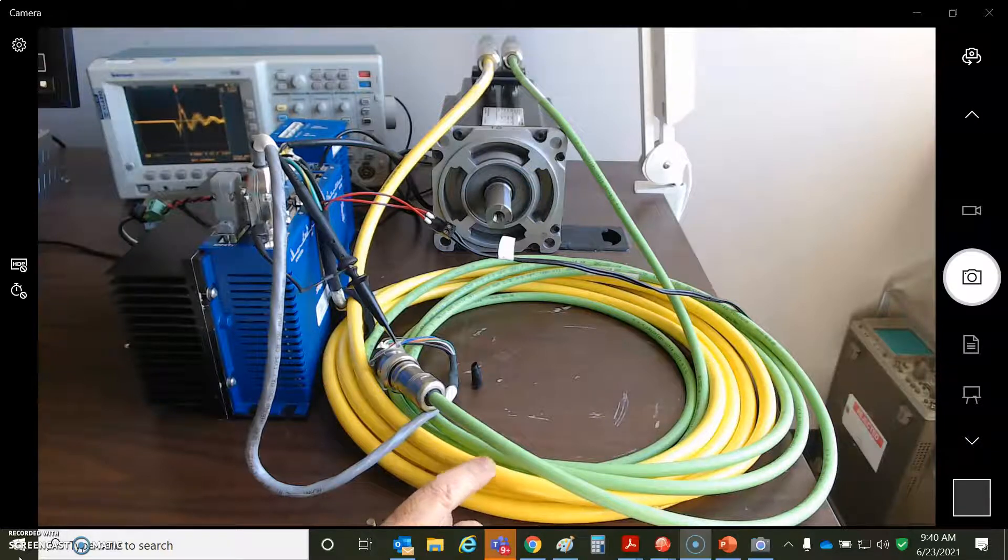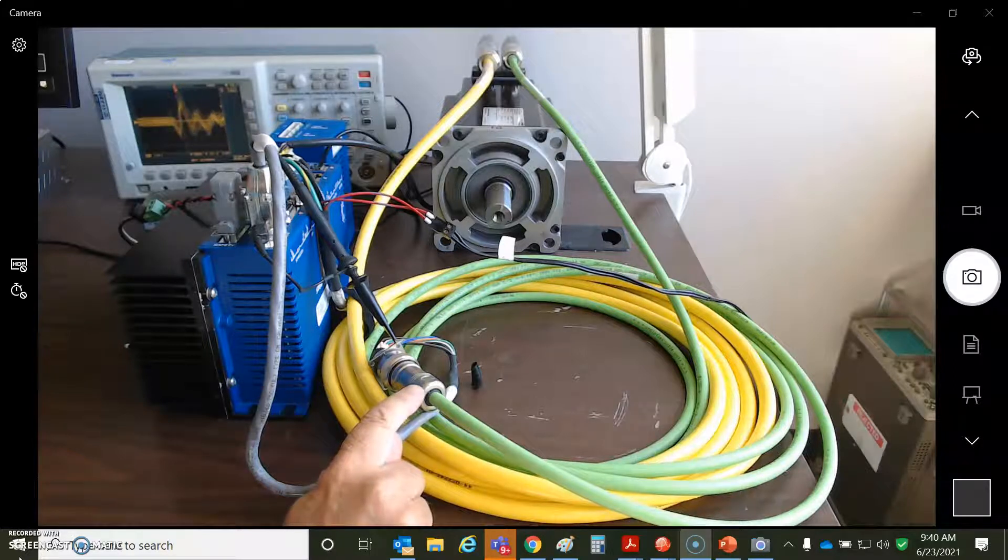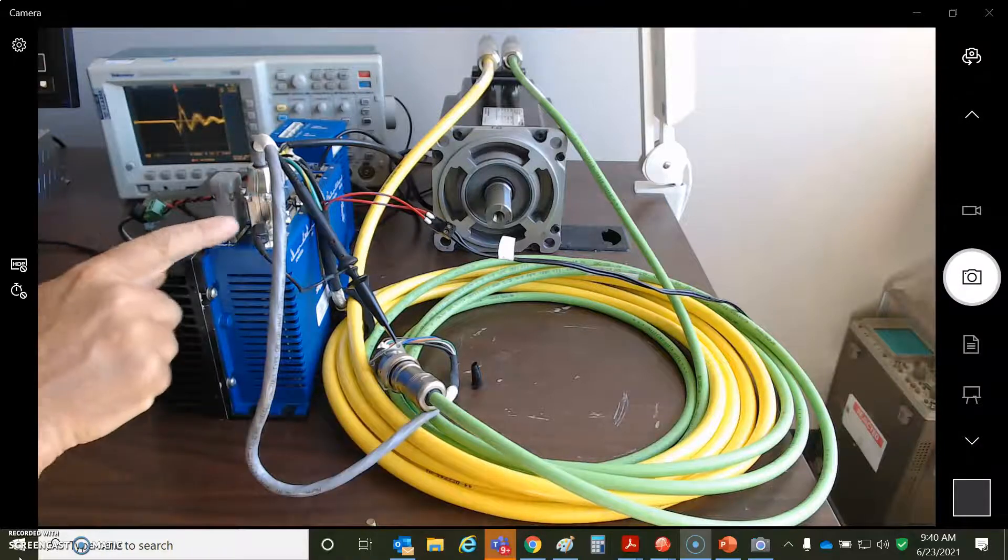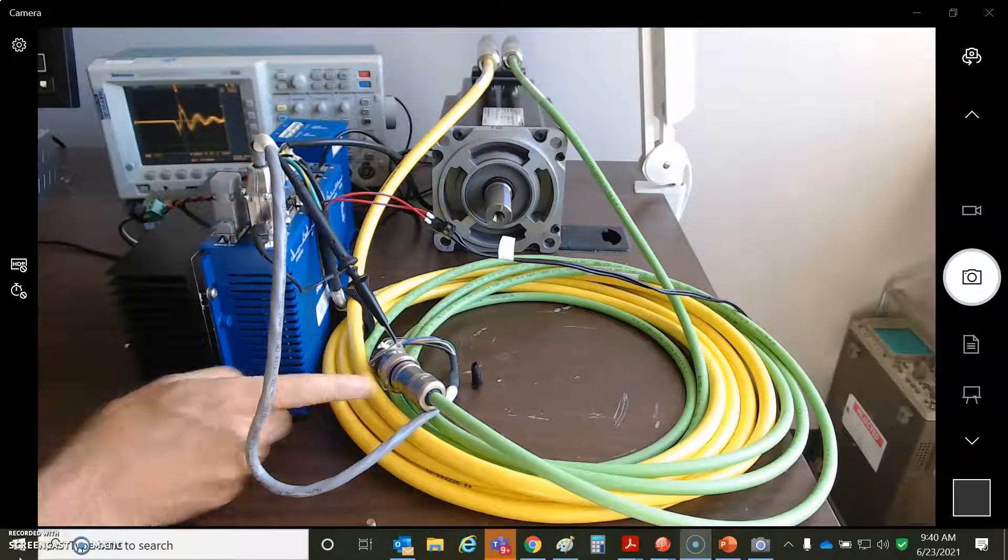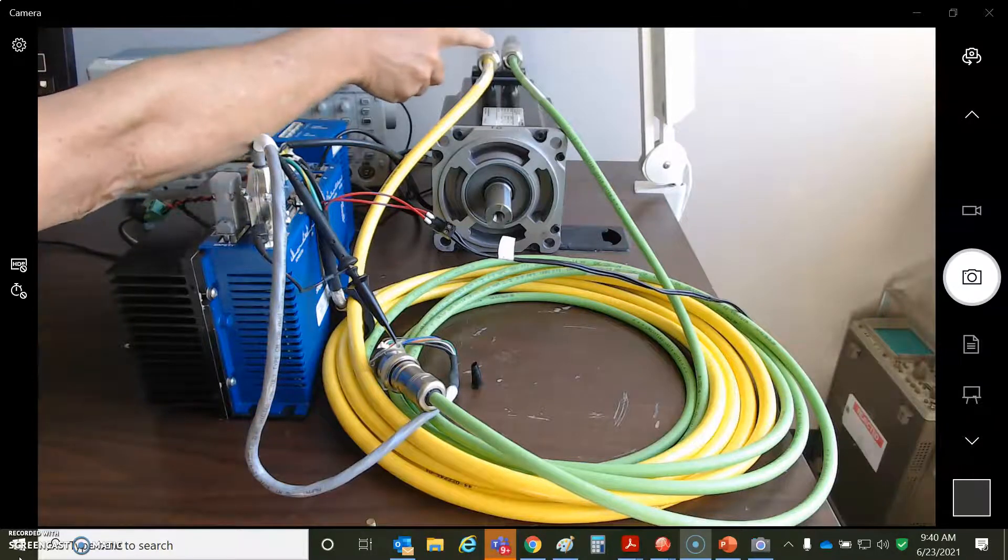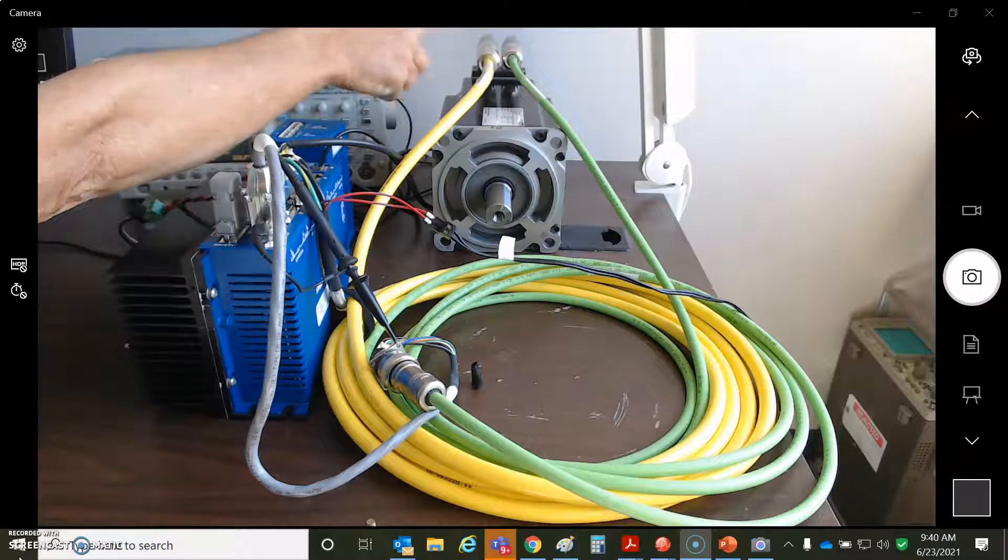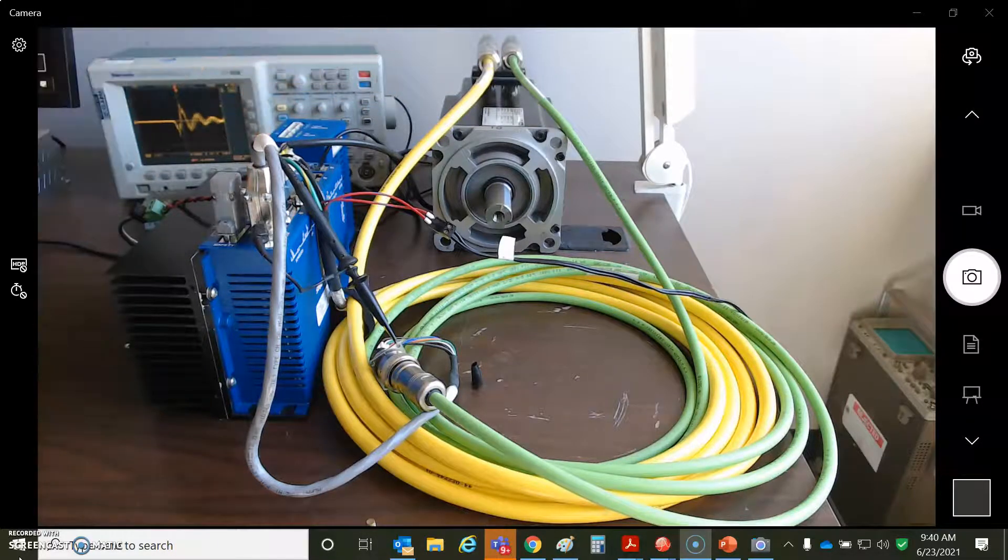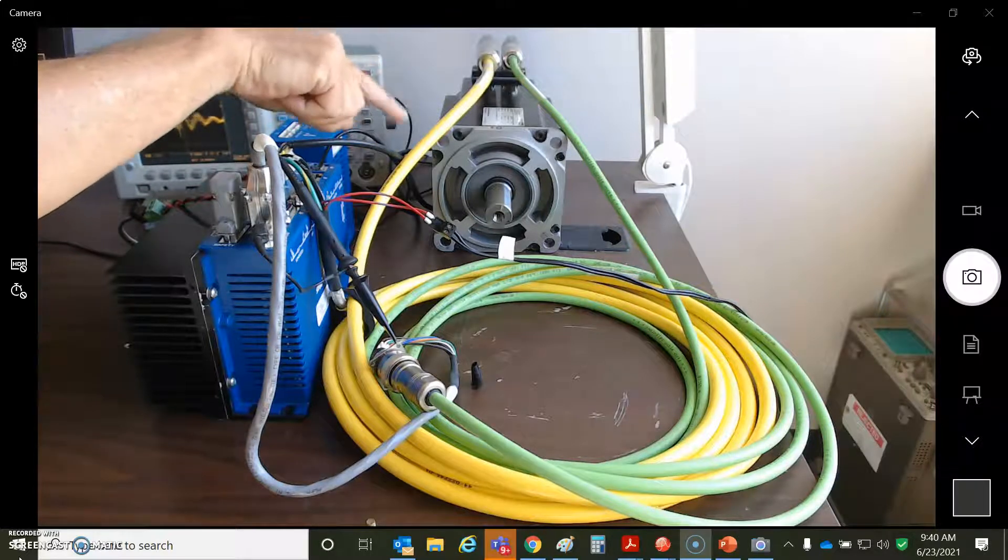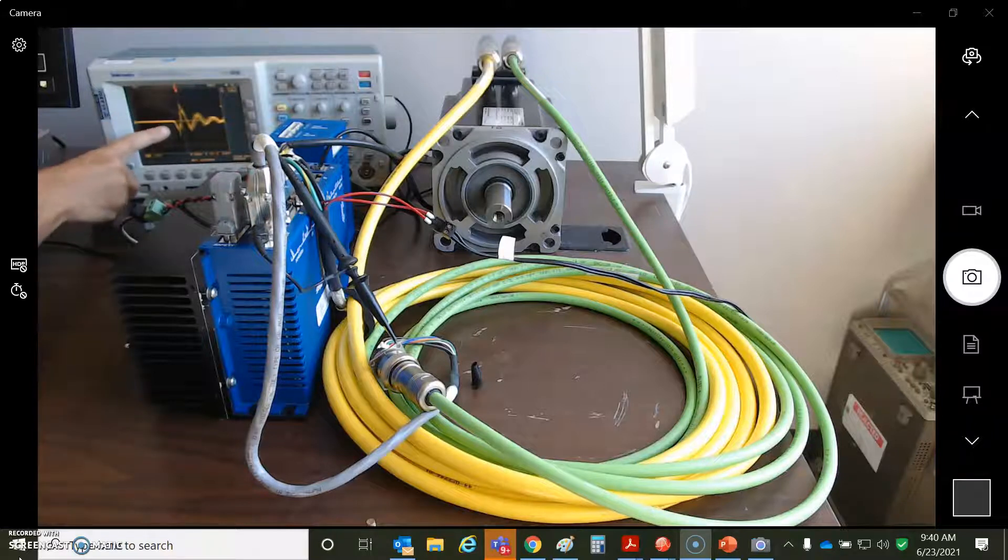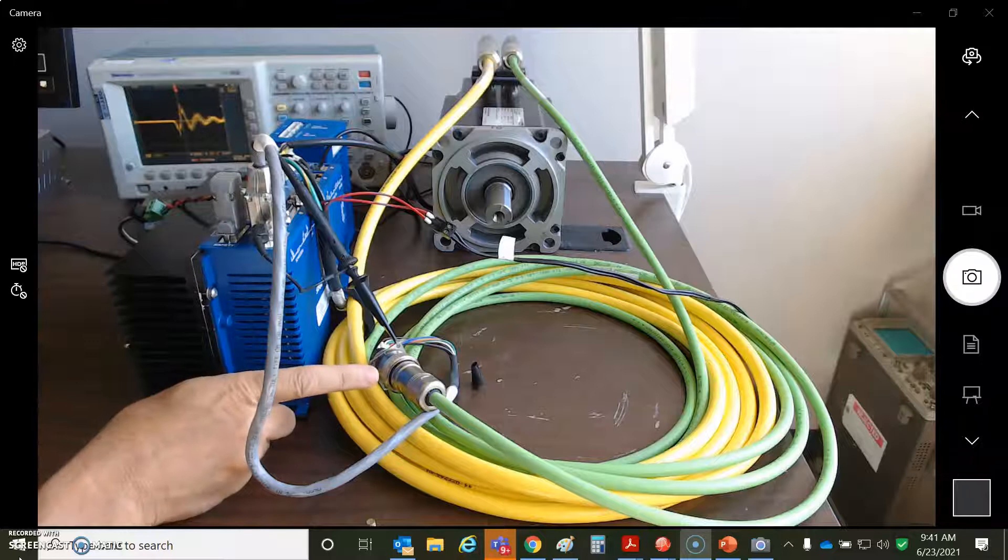Now, in this system here, I found that the shield was not connected at this end, which is the drive end. So there's an open between here and the shield. However, the shield is connected to the motor case. So it does find a path to Earth, but through the case of the motor back to the drive. That's kind of the electrons will still find their way down the signal. So this is why we see several volts of PWM noise on the shield.